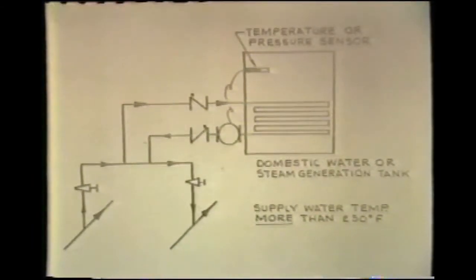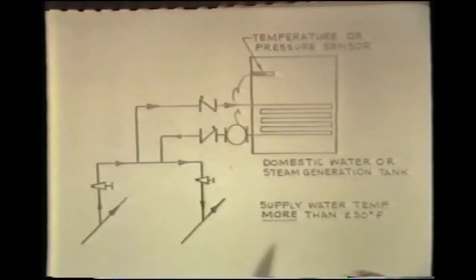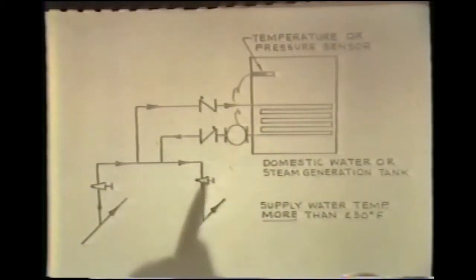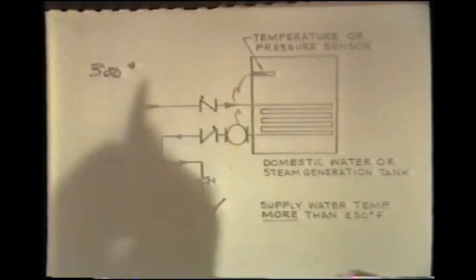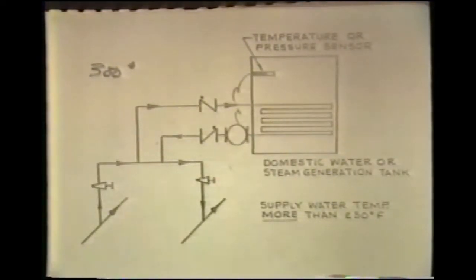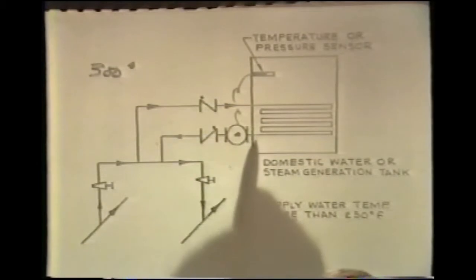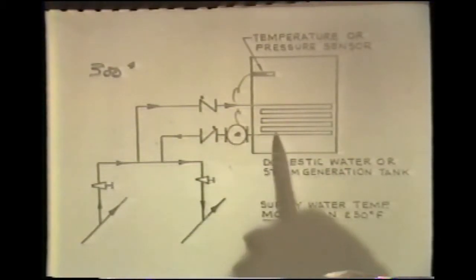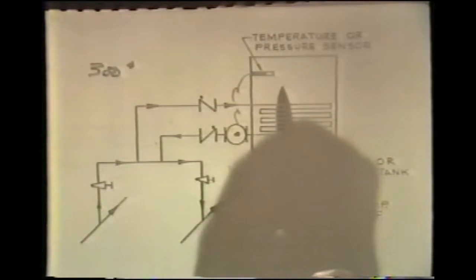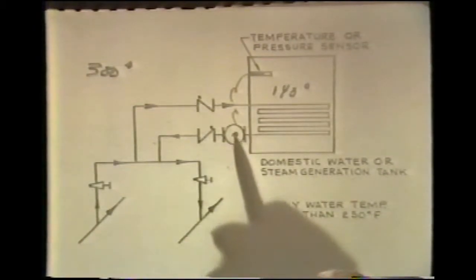In many cases, primary-secondary pumping has been used for very high temperature systems, at times corresponding to the order of 300 degrees Fahrenheit, or over and above low temperature, low pressure code limitations. But we can use a small secondary pump in an application such as this by simply placing the pump on the return side of the secondary circuit. Because so long as we are providing water in the storage tank at, let us say, a temperature of 140 degrees, the pump will not be subject to the high temperature limitations otherwise imposed on that pump.